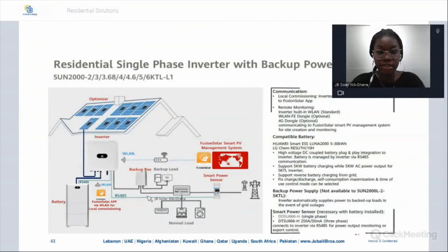Then you have the grid, because the backup box will see the grid and it will say, oh, the grid is down. Let me switch to battery mode. Oh, the grid is back on. Okay, let's switch back to grid tied mode. So the same inverter is doing both off grid and grid tied with the help of the backup box, and then to the inverter. So all of this is connected in here.